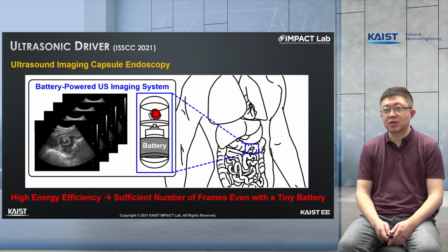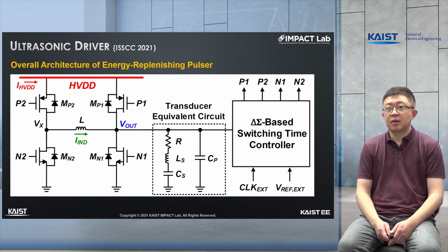Recently, we also developed the ultrasound transducer driver having extremely high energy efficiency. It was developed for ultrasound imaging capsule endoscopy that badly requires high energy efficiency to take a sufficient number of ultrasonic image frames while operating with a very tiny battery fitting inside the ingestible capsule. This is the overall simplified circuit diagram of the developed ultrasound pulser IC. This new circuit structure replenishes a major portion of the energy used for driving the ultrasound transducer. As a result, it can achieve a very high energy efficiency.